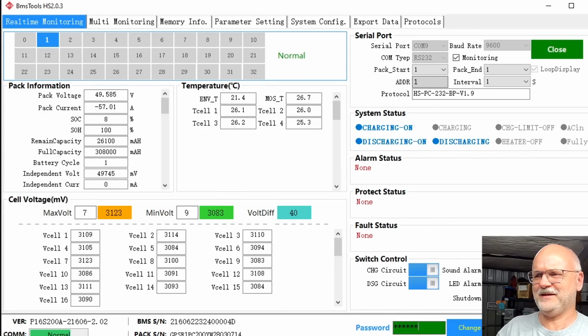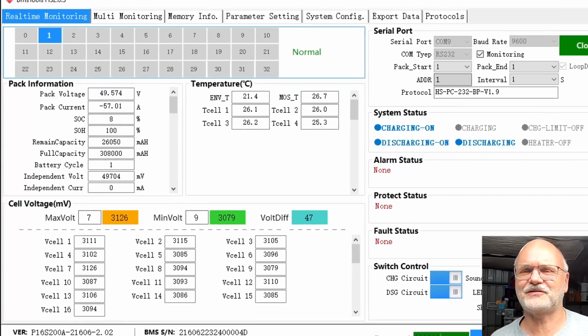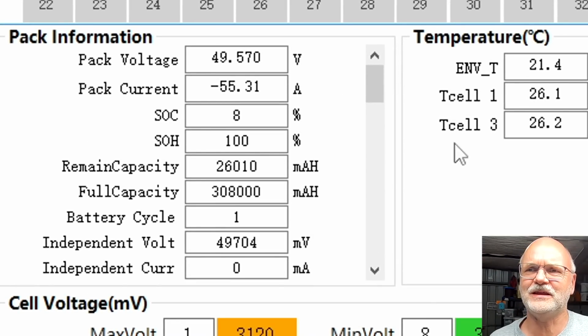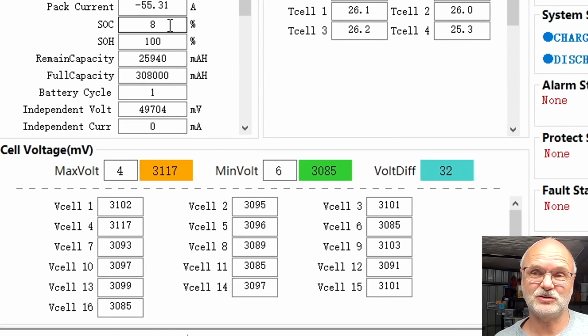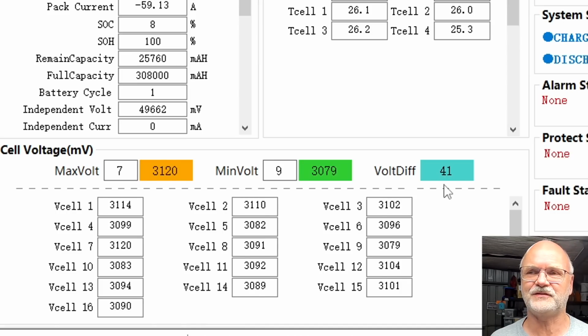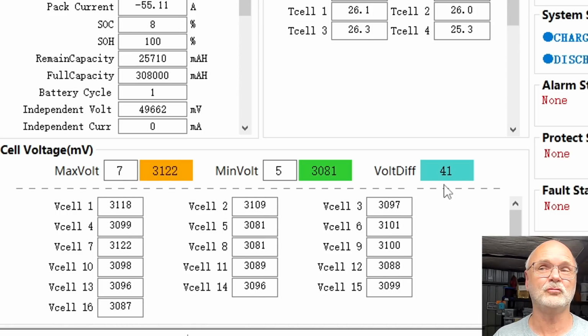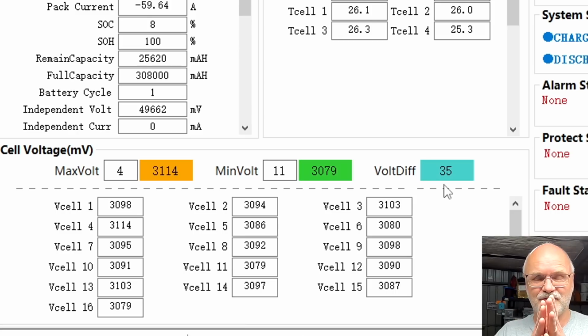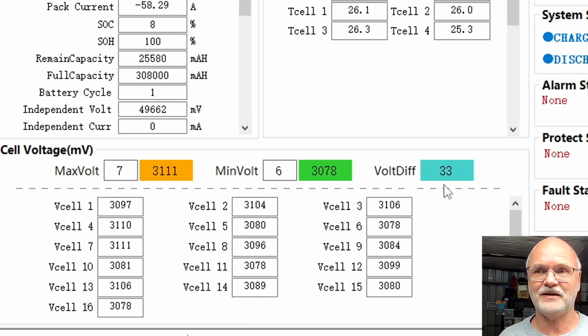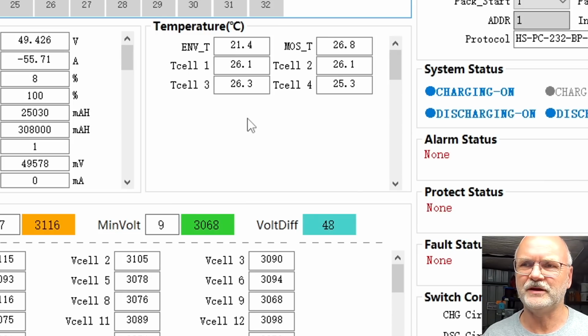Alright my friends, it's already close to 9pm, the test is still going. We just dipped under 50 volt pack voltage, discharging at 55 amps, with 8% state of charge left. Down here the deviation is at 35 millivolts but slightly increasing now - it was 25, 22, 25 all the time, but now around 40, so it's slightly increasing. The cells are getting low and spreading apart now. Temperatures have almost not increased, but the current isn't high enough for that - even the BMS temperature is only at 27 degrees.